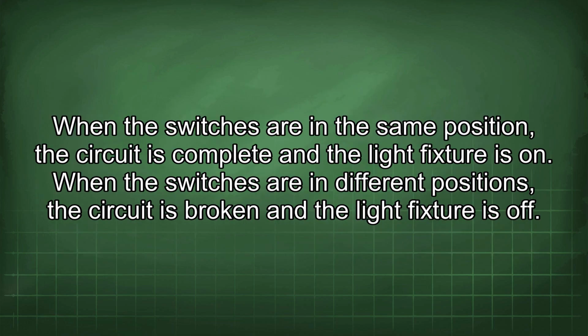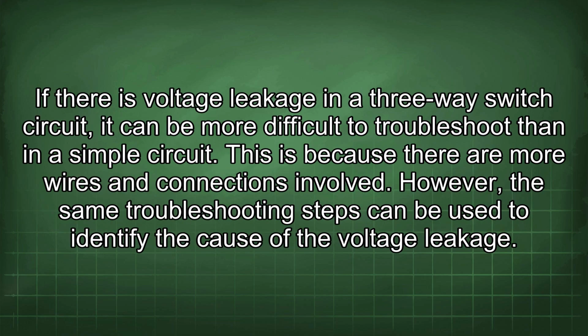When the switches are in the same position, the circuit is complete and the light fixture is on. When the switches are in different positions, the circuit is broken and the light fixture is off. If there is voltage leakage in a three-way switch circuit, it can be more difficult to troubleshoot than in a simple circuit. This is because there are more wires and connections involved. However, the same troubleshooting steps can be used to identify the cause of the voltage leakage.